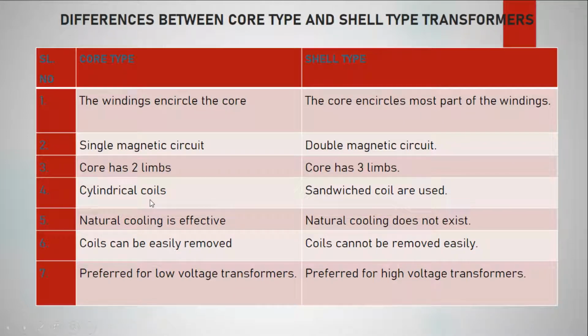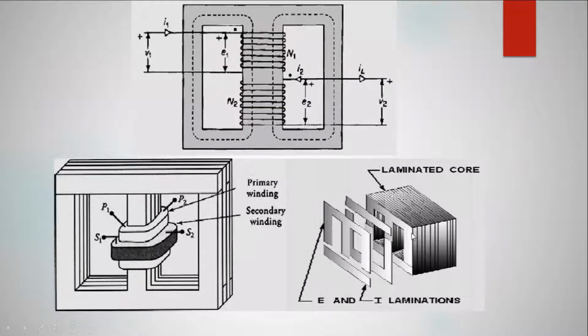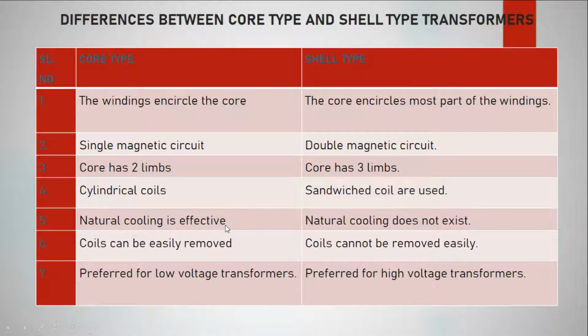In the core type, cylindrical coils are used; in the shell type, sandwiched coils are used. So what is meant by sandwiched? Here the primary and secondary are placed one over the other, just like a sandwich. They are perfectly insulated from each other and will never touch each other, but they are kept as a sandwich type of coils. In the core type, natural cooling is effective. Here natural cooling does not exist in a shell type transformer, so natural cooling will not be provided.